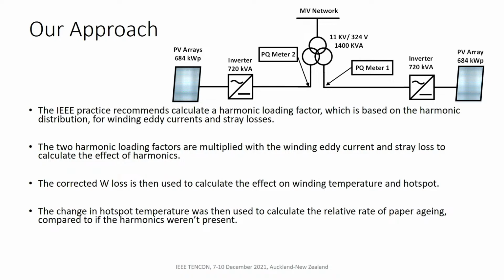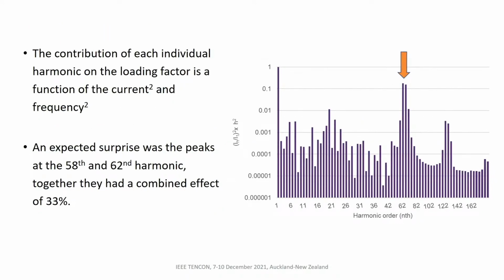So we calculate our harmonic loading factor, and we multiply it with the winding eddy current, and then we can calculate the stray losses. And then when we know these total losses, we can calculate the temperature rise within the transformer. And then we can start to look at the relative rate of paper aging.